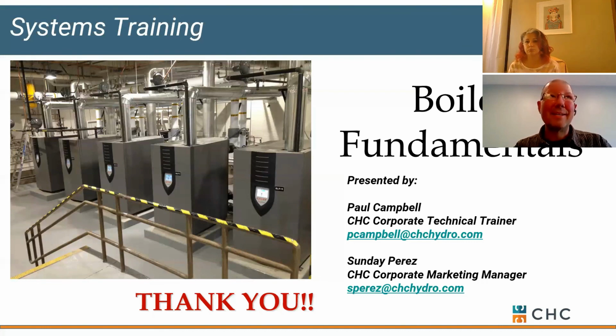If we want to talk about system volume, all that comes into water flow and the delta T we're designing out in the system. A lot of that comes into play if we're maybe more on the industrial than on the commercial side. But if you've got a process where you've got 10 tanks, but we potentially are only serving one, you might need some extra volume in there.